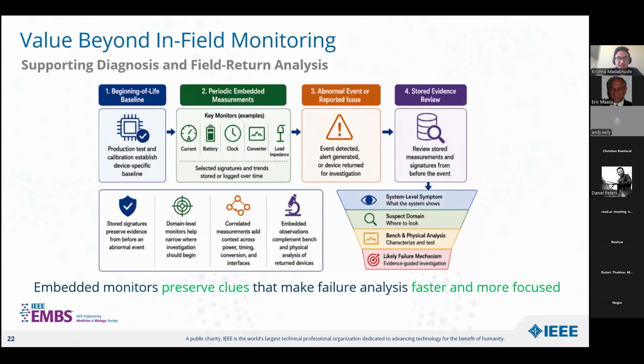So this is important because the condition that caused the problem may have developed gradually, appeared intermittently, or disappeared by the time the device reaches the laboratory, right? So a returned device often shows us only the present state of the device. So the stored history may help us show what changed before that event actually occurred. The history may, for example, show a sudden increase in current or a rising battery impedance or a converter drift or an impedance change. But none of these observations necessarily identifies the root cause itself. But they provide a small piece of information that we can use during failure analysis to build a bigger picture. And it'll also help the failure analysis team in the future to narrow down the issue.